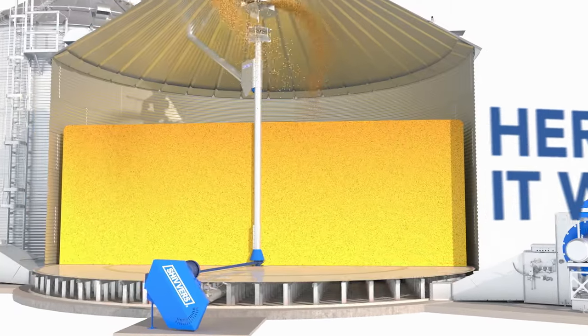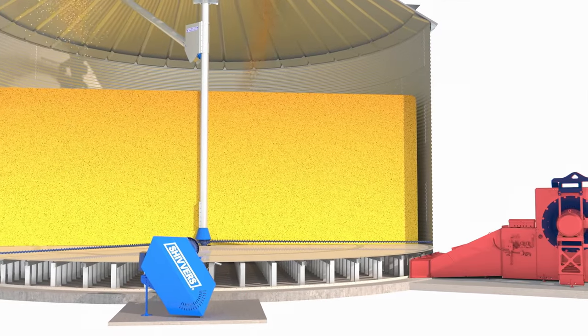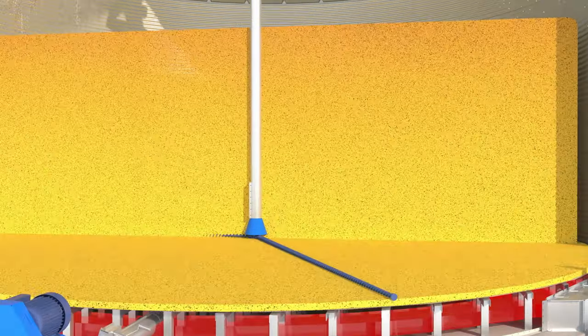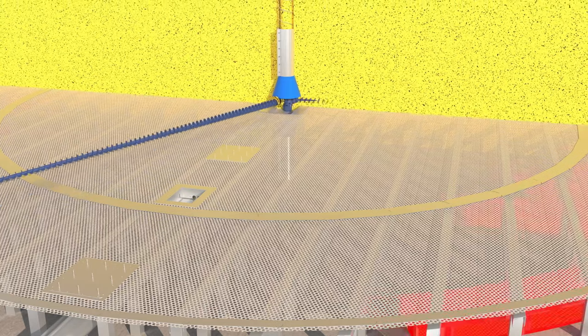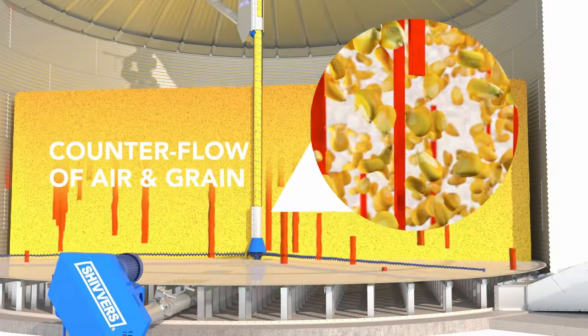The plenum, created by a raised perforated drying floor, is heated with Shivvers Blue Flame heaters. As heated air flows upward, tapered sweep augers remove an even layer of dry grain, moving the wet grain into the primary drying zone. This counterflow of air and grain gives you several advantages.